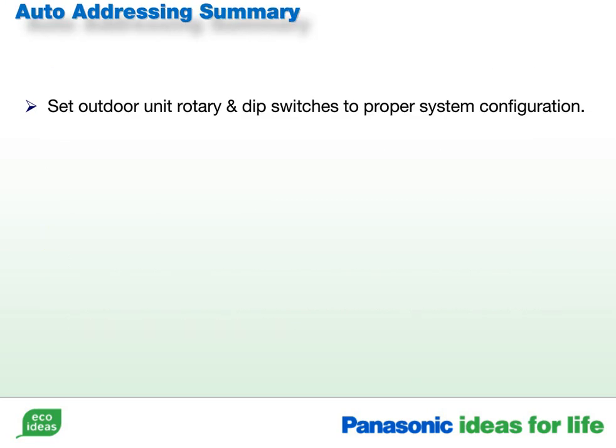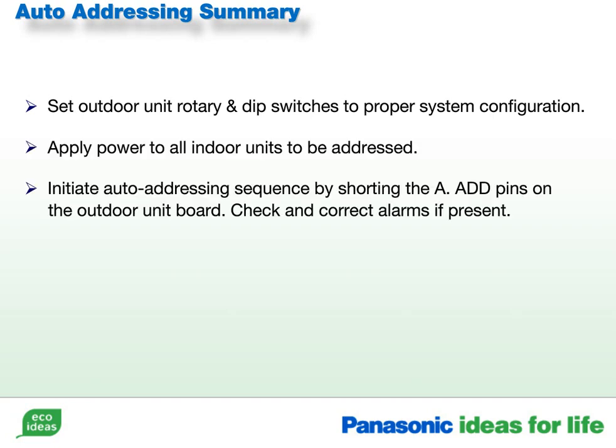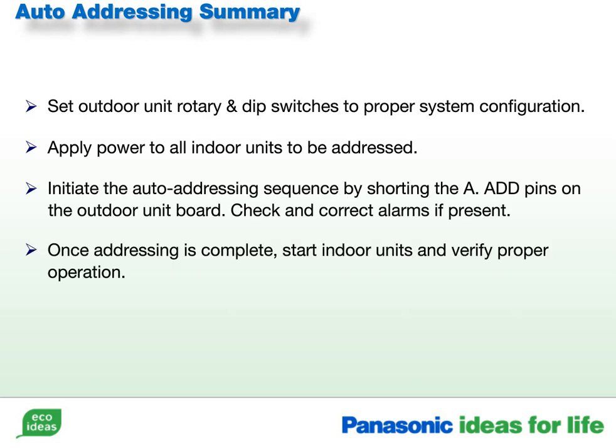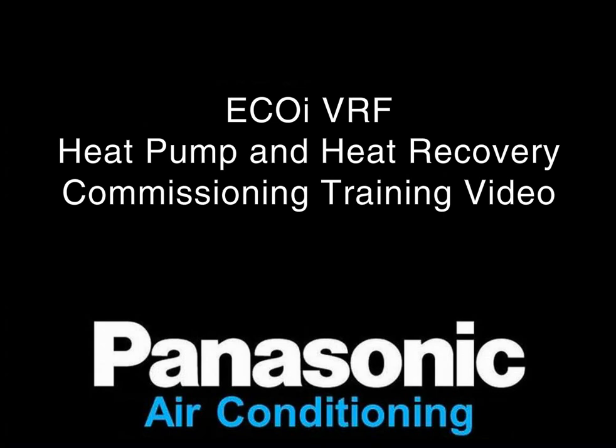Summary for the auto-addressing procedure and test run. Set the rotary and dip switches to the proper system configuration. Apply power to all of the indoor units to be addressed. Initiate the auto-addressing sequence by shorting the A.ADD pins on the main PCB in the outdoor unit. Correct any alarms if present. Once the system has addressed, perform a test run and verify proper operation. This concludes the ECOi heat pump and heat recovery commissioning video.